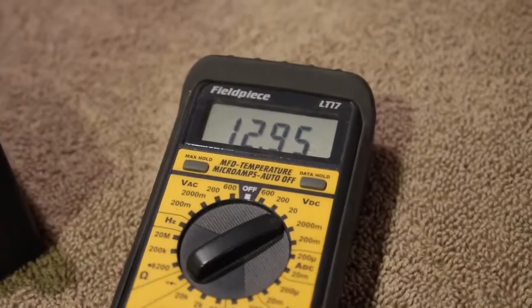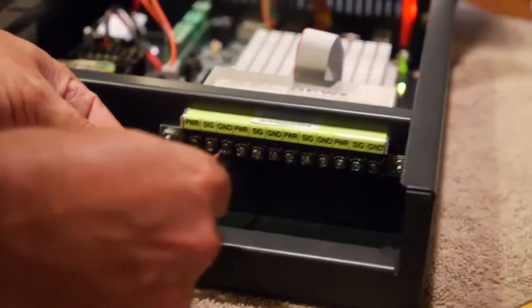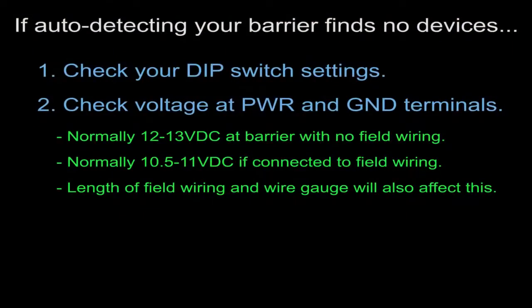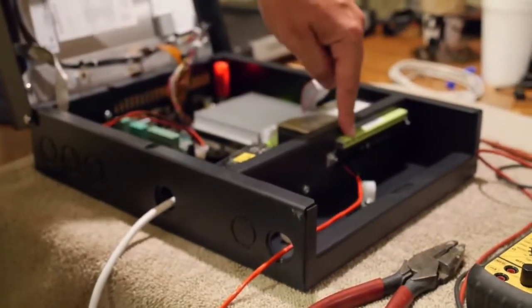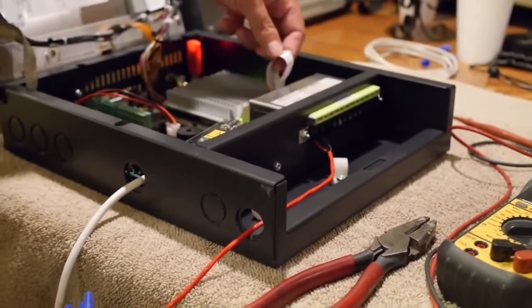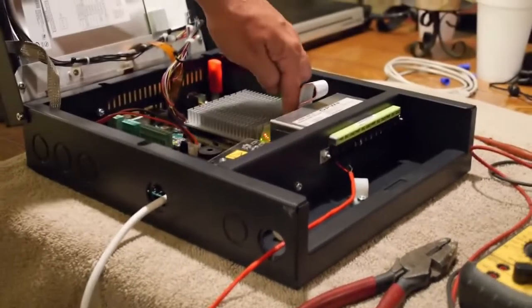Now I'm going to read between power and ground on one that I have 2 probes connected, and you can see that it's about 11.5 to right at 12 volts. Depending on the length of the cable running from the console to the probes, you can be down at 10.5 to 11 volts on this particular cable. If you read the barrier voltage on the barrier as well as the good barrier, and you see that you have voltage and it's not at 0, then you should be okay. If you don't have voltage on the barrier itself, make sure that the ribbon cable is plugged in snugly on the board.